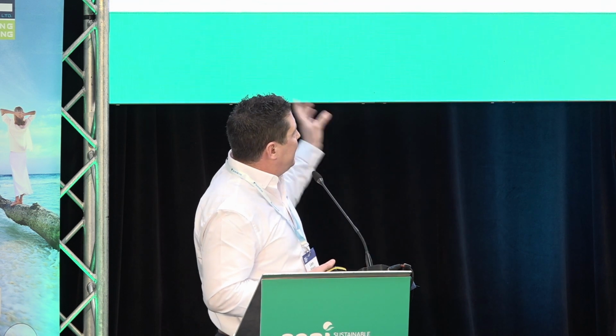You can see in blue is R410A, and the exact same system, same horsepower, in red is R32. So what you can see is the data taken from the two same systems, same applications, in a typical office block, I think this was. We recorded it over the same amount of time. You can see up to a 14% increase on the seasonal data and up to an 8% increase on the average of the SEER and the SCOP, which is based over the heating and cooling of the system running in the same conditions. So you can see that R32 is a much more efficient gas than R410A.